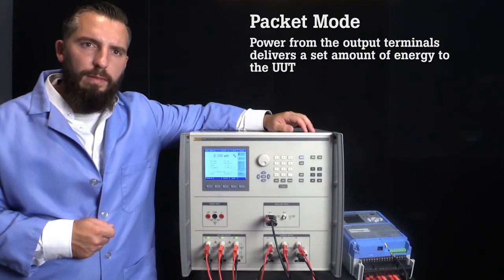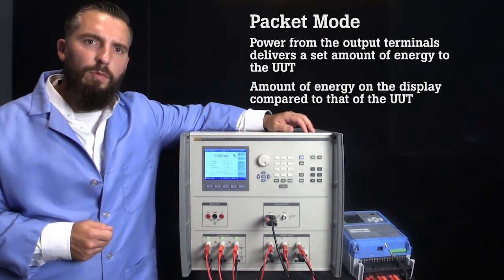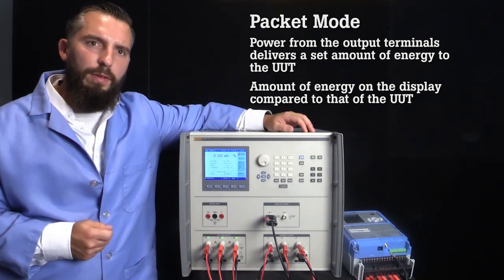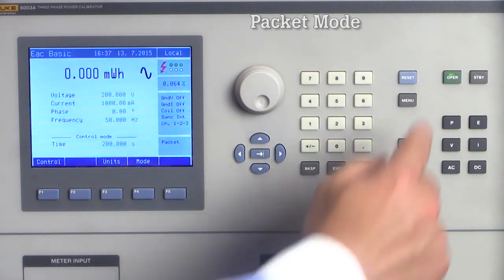To test the accuracy of the meter, the amount of energy shown on the display will be compared to that of the energy meter and the deviation must be manually calculated. Using this energy meter, I will run an example packet test which will let me determine if it measured and reported the correct watt hours. I have configured my test for 200 volts AC, 50 hertz, and 1 amp. I will set the packet time for 200 seconds. I have also prepared the meter to start measuring from zero. I will now push operate and you will see that the test starts and the countdown begins.